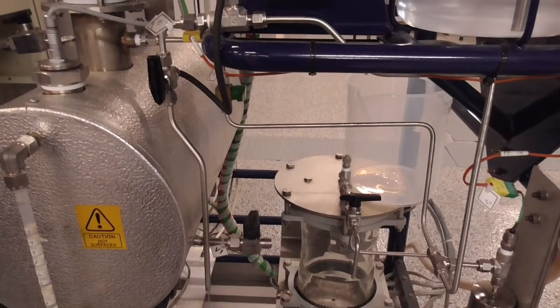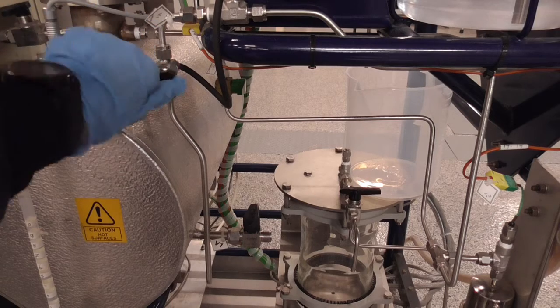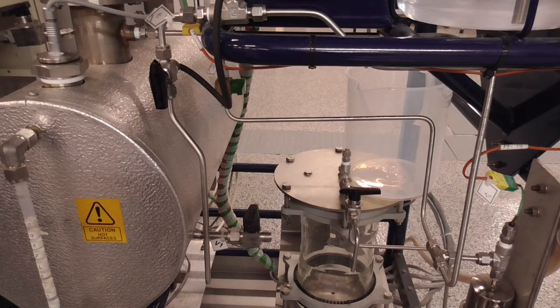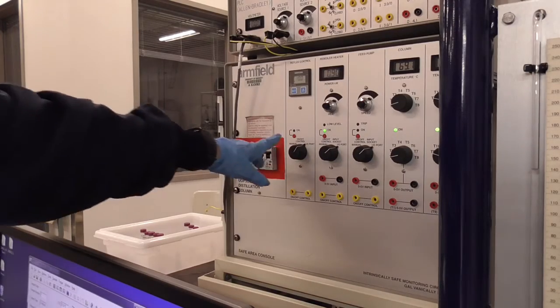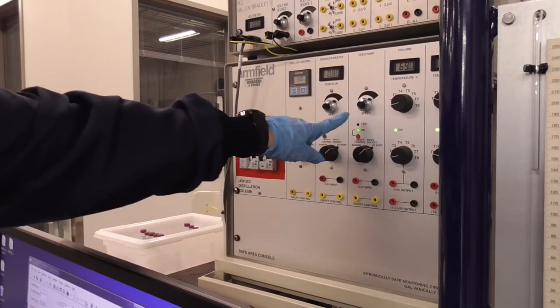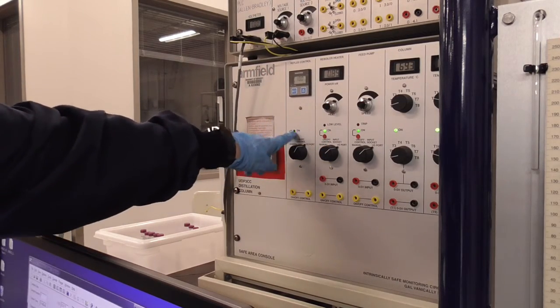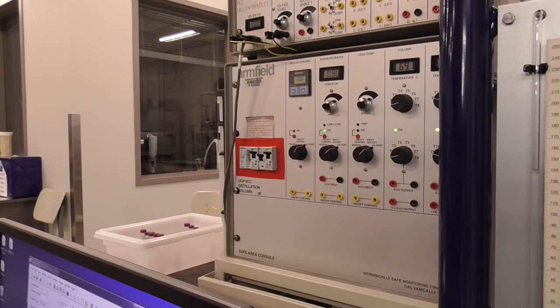Once you are finished with the calibration curve, be sure and turn your three-way valve back into the system by pointing up, and you can turn the feed pump off at the red button until you're ready for feeding. Anytime you don't need the feed or reflux, you can just turn them off quickly here at the control panel.